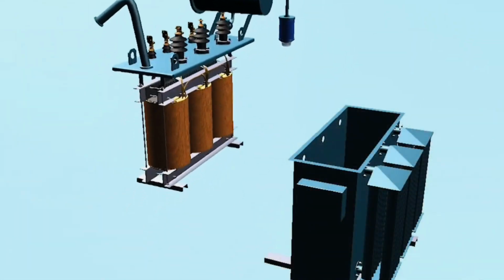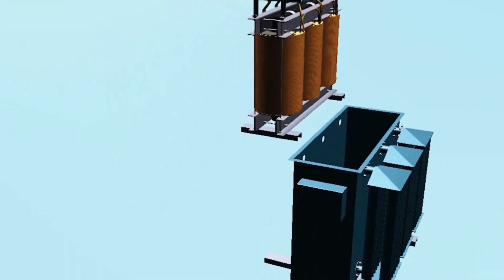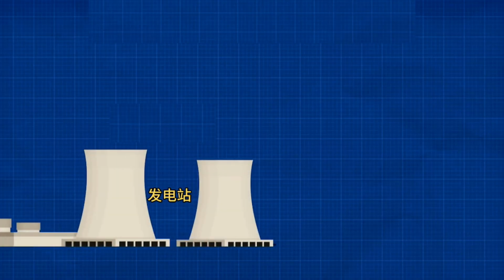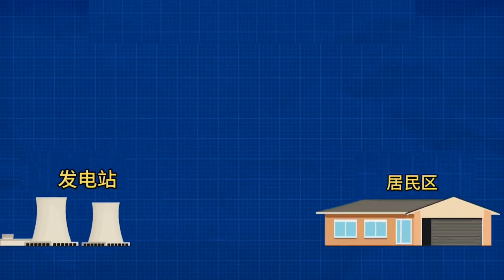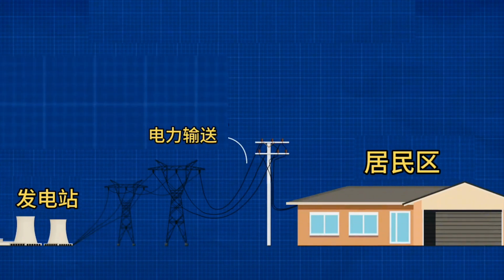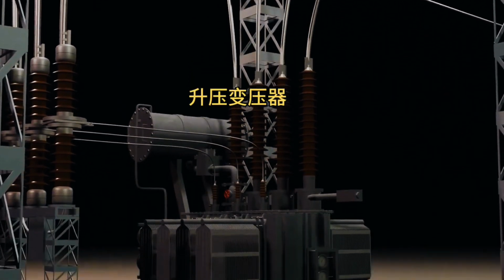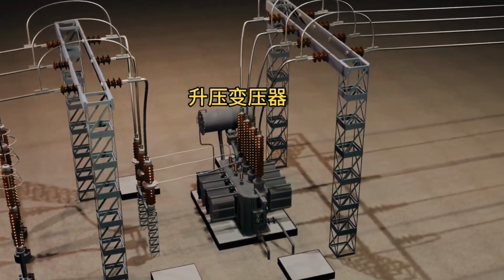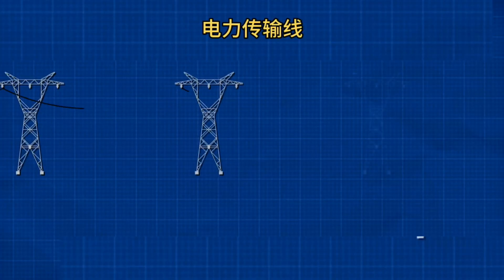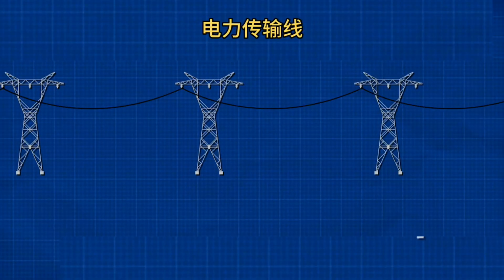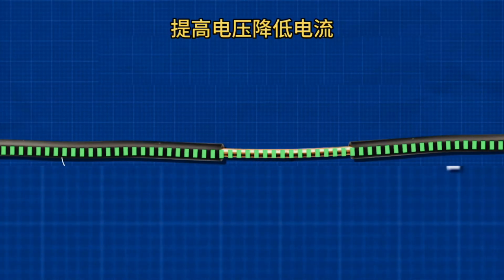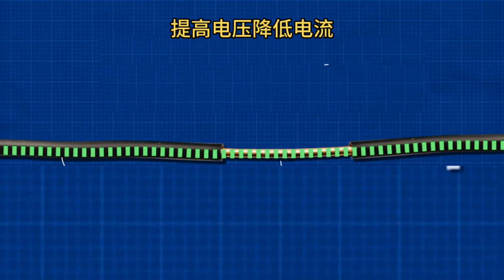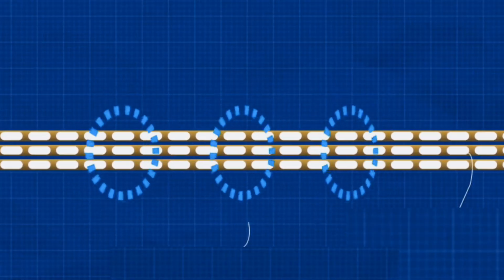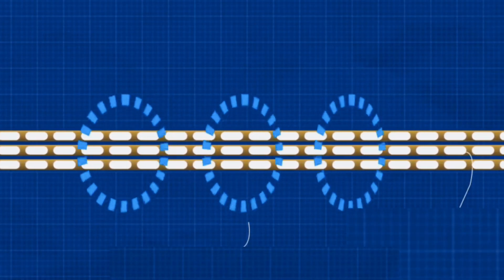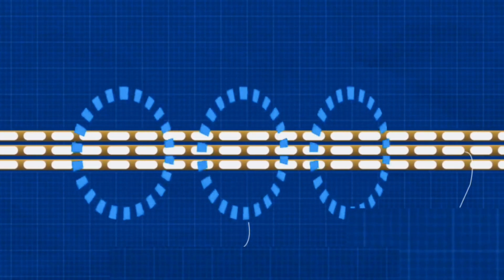Before understanding its working principle, let's briefly introduce the function of a transformer. For example, a power station needs to transmit the electricity it generates to residential areas at a certain distance. The station will use a step-up transformer to increase the voltage and reduce the current. This is because the resistance and inductance on the transmission lines can cause power loss. But according to Ohm's law, increasing the voltage can reduce the current on the transmission line, and lower current can decrease inductive losses on the line. By increasing the voltage, power loss is reduced.